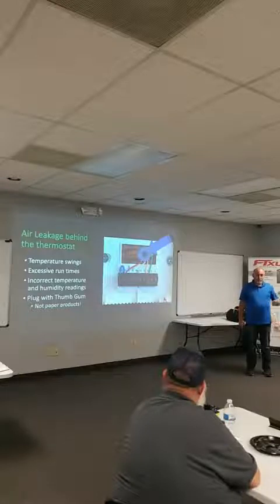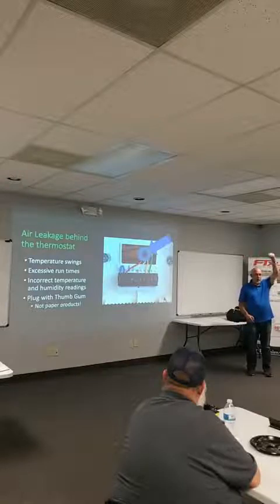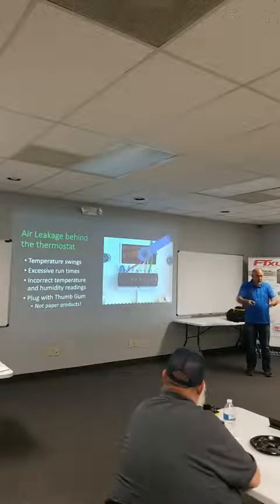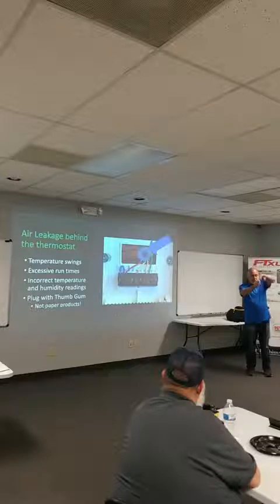Now, the guy goes to put the thermostat wire in, he uses a 1.25 bit, drills a hole up to the floor joist, and runs the thermostat wire down to the wall. He doesn't want to make a little tiny hole he has to fish the wire through. He's going to make a big honking hole in there. He's got supply leakage, the ductwork's torn down, it's pressurizing the crawl space, and it's pushing the humid air right up through that thermostat chase. Literally, you could hold a lighter out there and see the flame bending out like this. I'm like, dude, you gotta plug that.